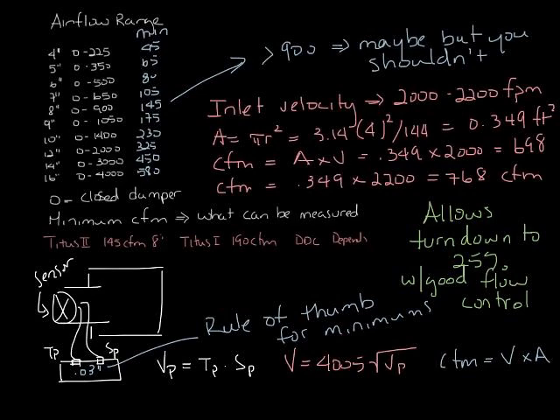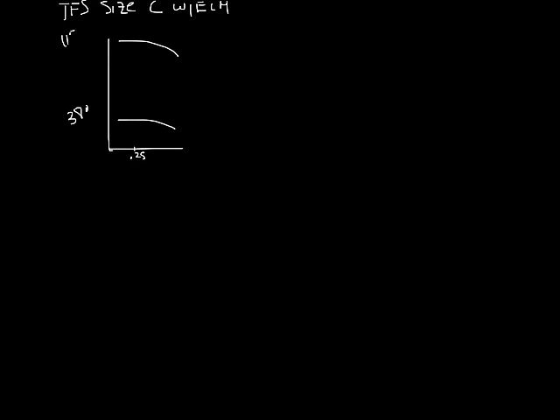So if you're sizing a single duct box or a dual duct box, because the inlet size equals the unit size, you're pretty much done. In a fan box, the inlet size is only half the unit size. So now let's talk about how to size the fan in a fan box. I discussed this some in the podcast on fan curves. A fan curve looks like this. For a TFS casing size C with an ECM motor, the minimum fan CFM is about 380 CFM at 0.25 inches, and the max is about 1150.